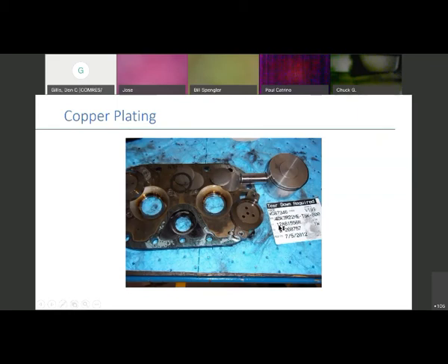We always teach the students what this serial number says. The first two are the year that it was made. The letter here is the month. So we're looking at January 2012. And look at this, how when this compressor came back, July 5th of 2012. So that was a very short time that it was out there in the field. And obviously it was in transportation.